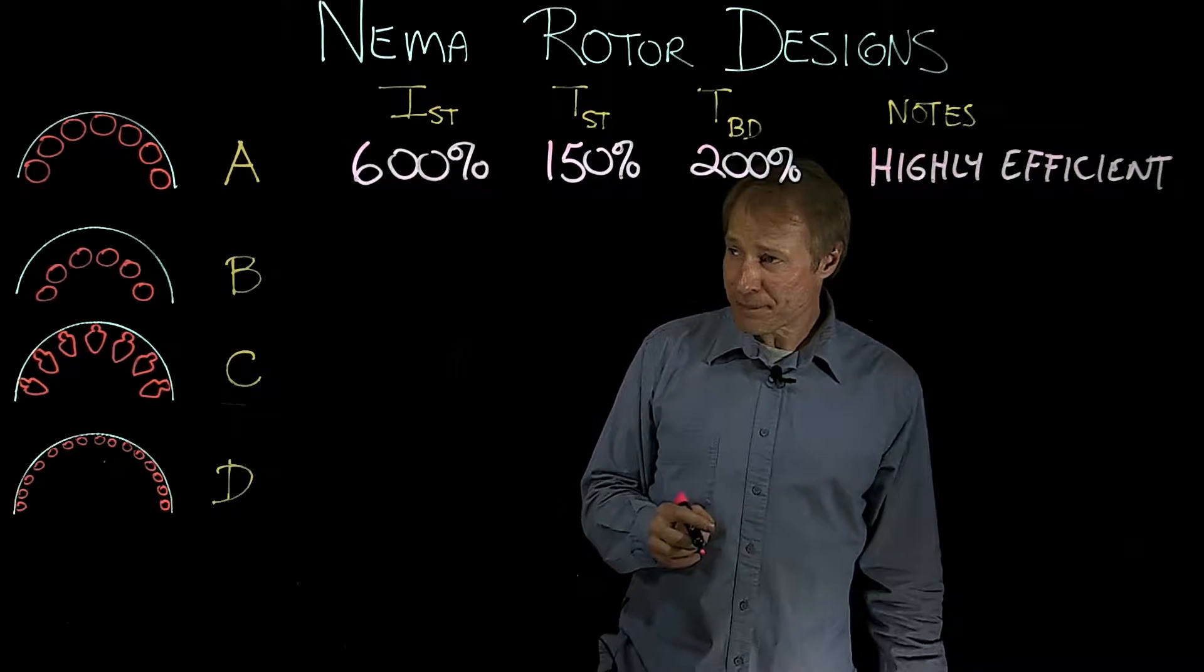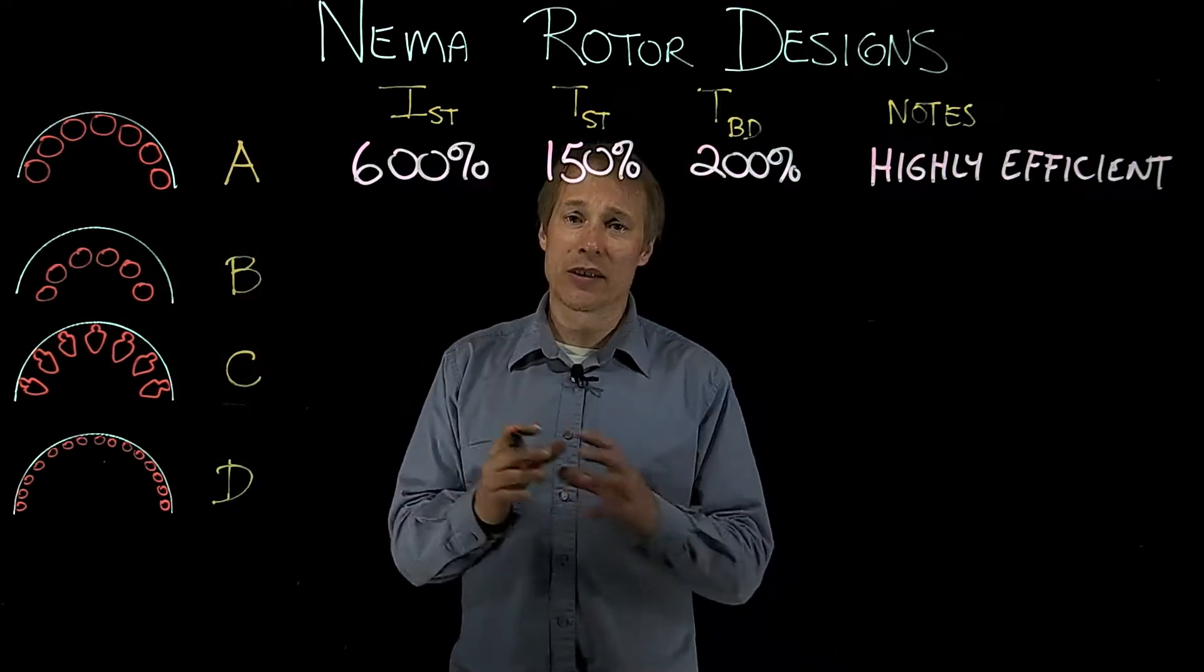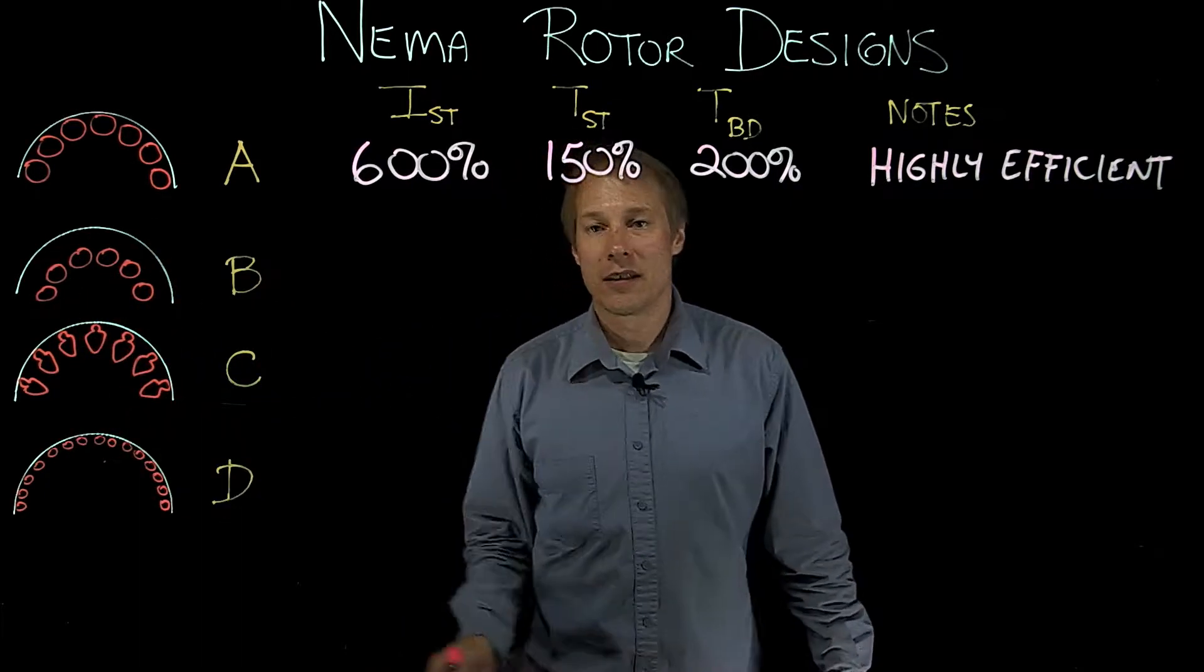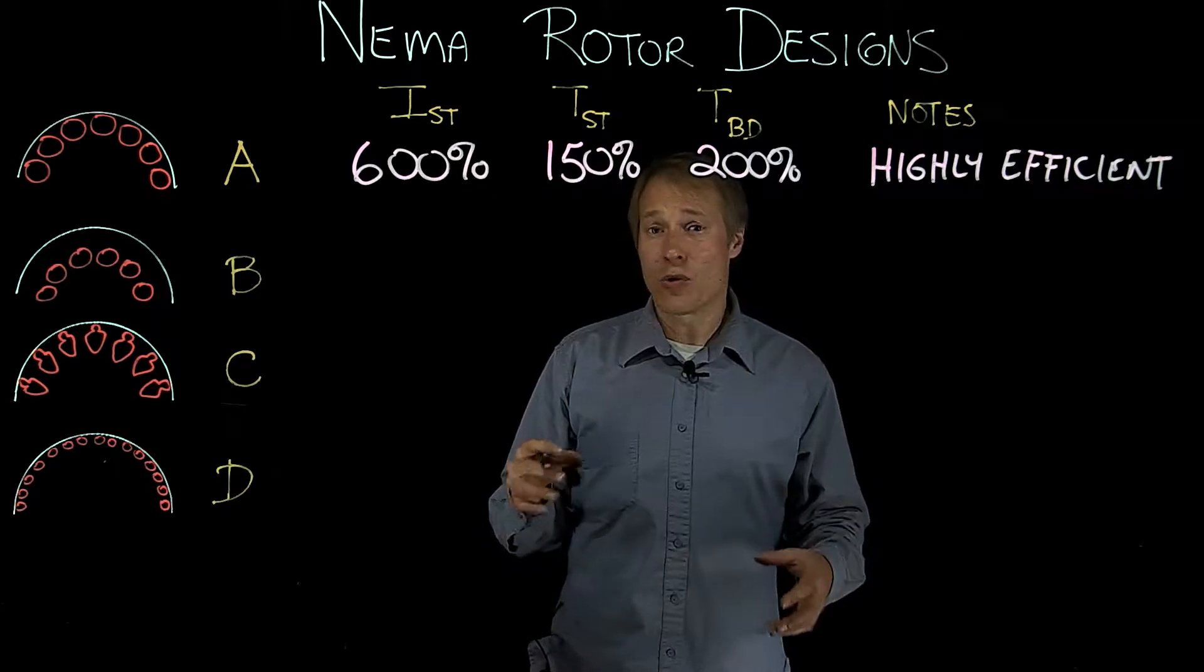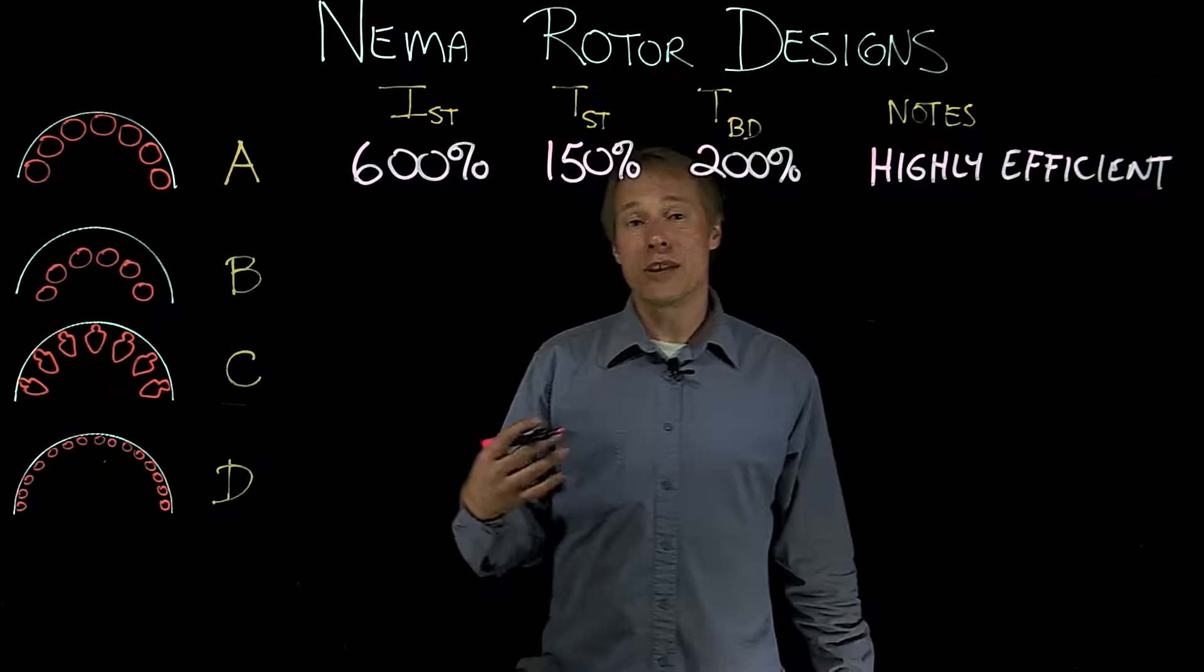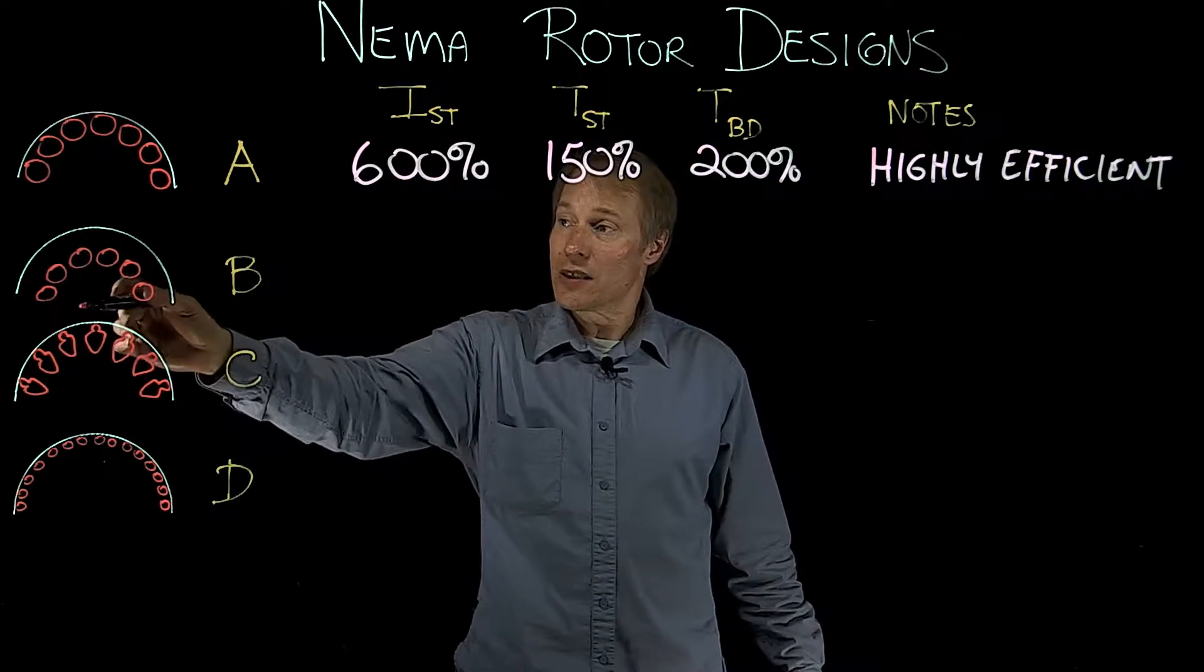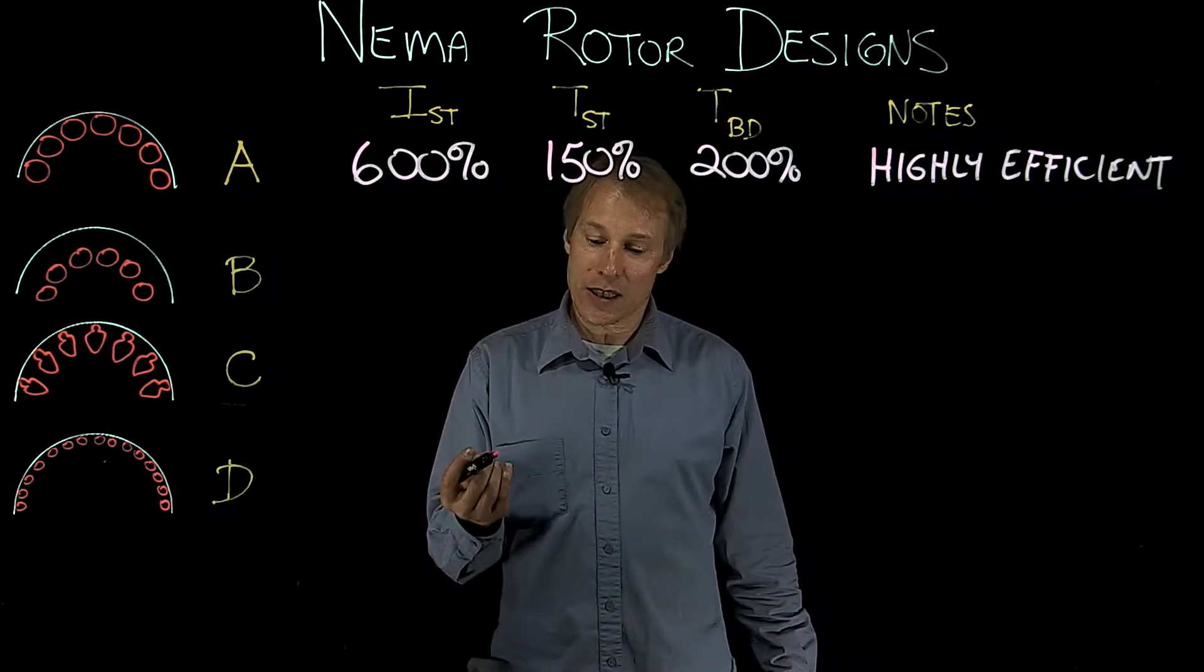Let's move on to rotor B. Now the difference between B and A is the rotor bars are the same size, but they're brought back from the edge of the rotor a bit and they're embedded in the rotor more, which changes the inductance, or it actually increases the inductance. And that will increase the inductive reactance. Now the resistance is going to stay the same, as you can see it's the same size bar. So the resistance stays the same.